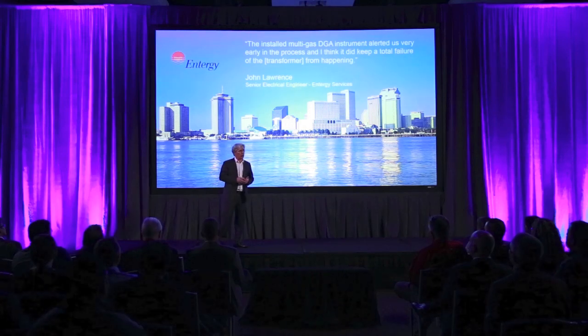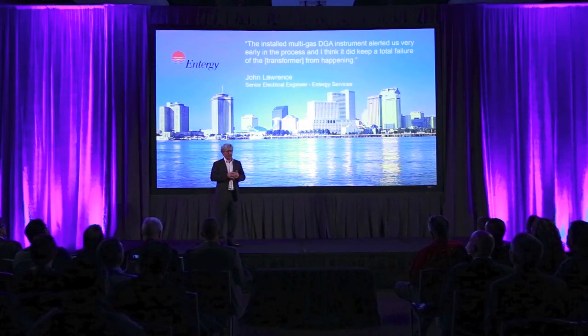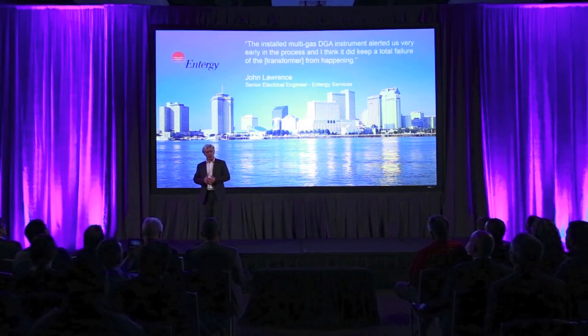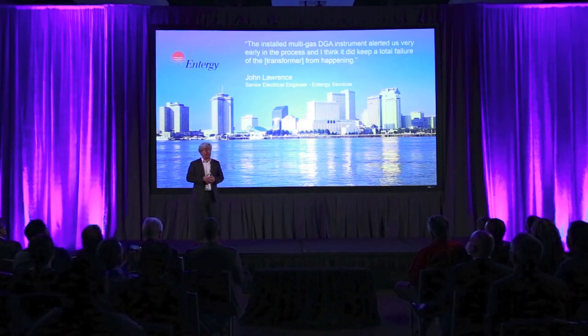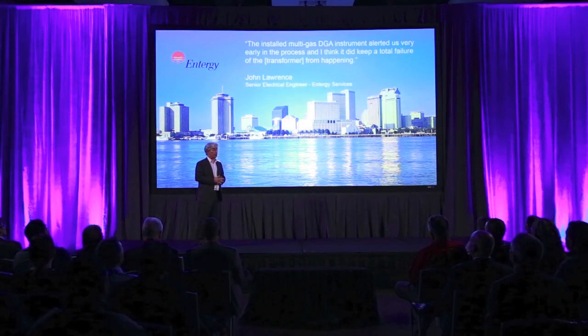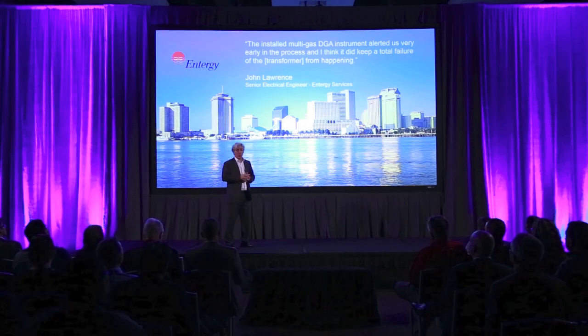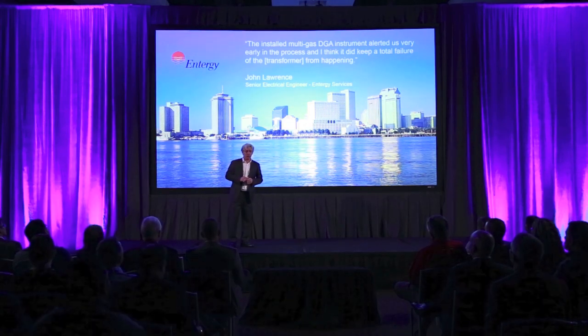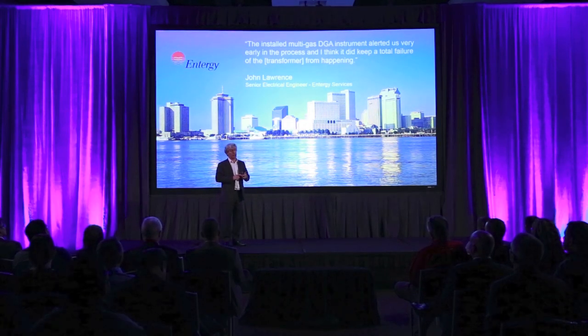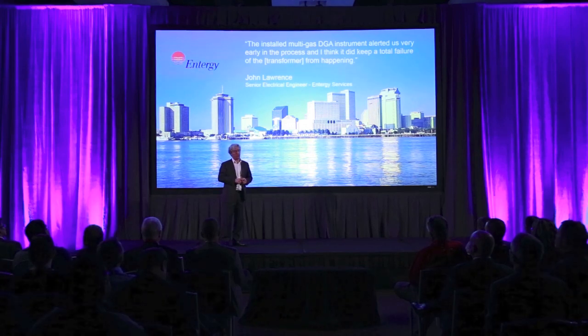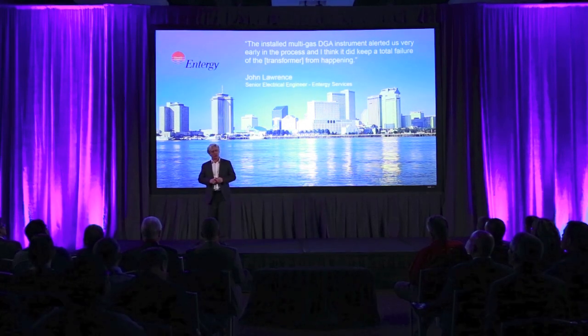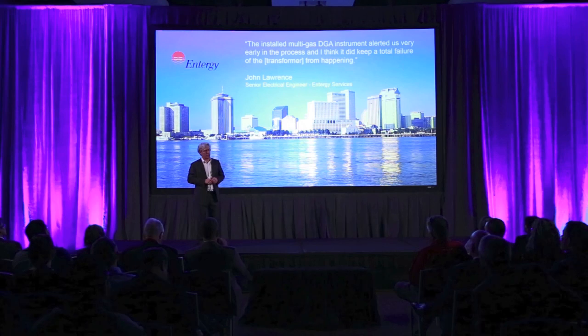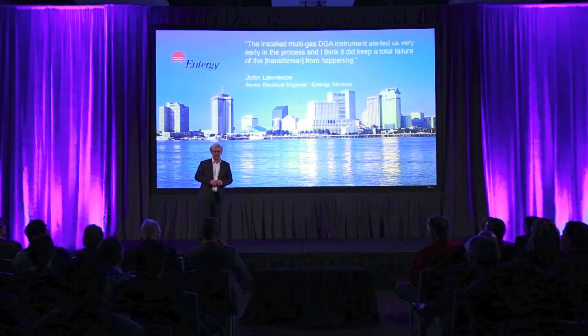John Lawrence, senior electrical engineer at Entergy Services, provided us with the following feedback. The installed multigas DGA instrument alerted us very early in the process, and I think it did keep a total failure of the transformer from happening. We used manual samples to cross-check and verify the installed multigas DGA instrument, and the lab results supported what the installed DGA instrument was telling us.